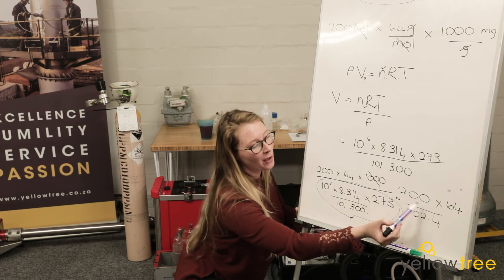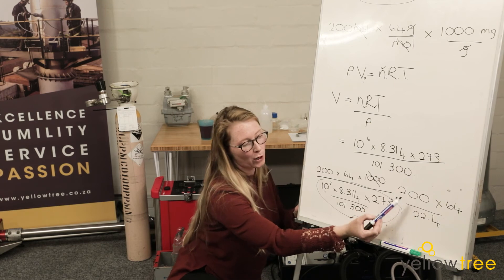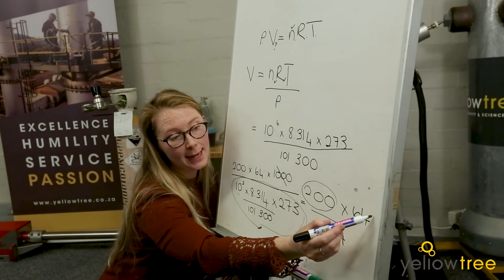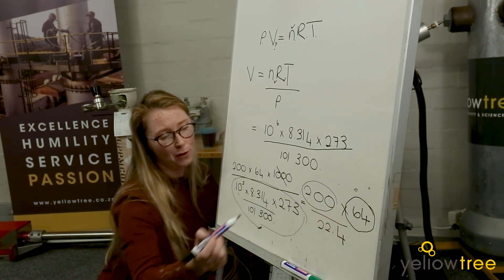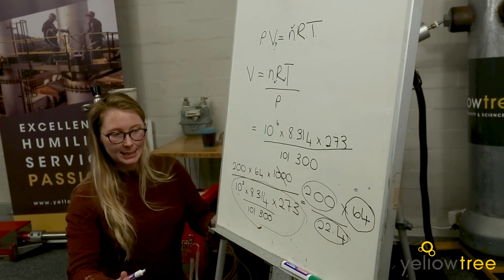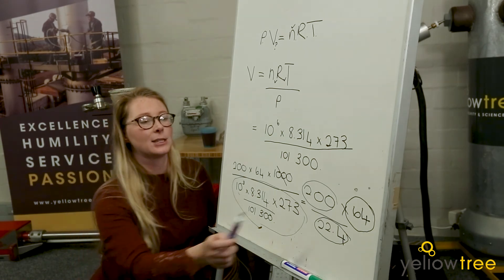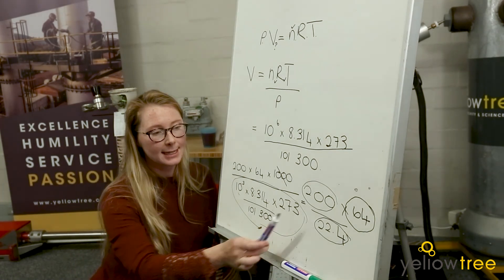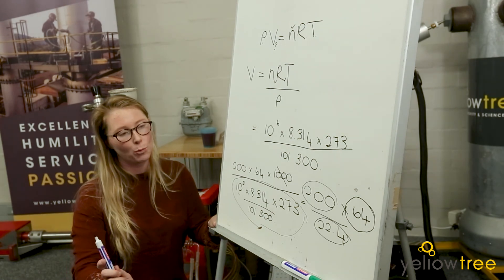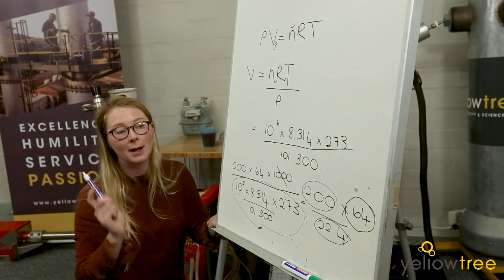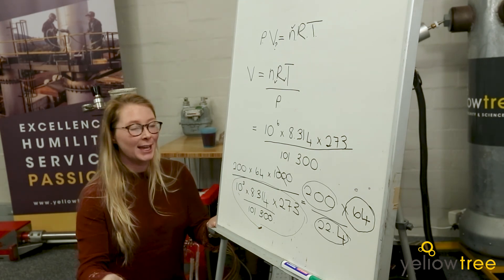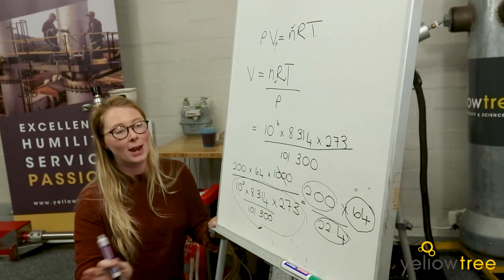So you can see we have the original ppm value we were working with — in this case 200. We have the molar mass of the gas — 64 for SO₂. And we have the number 22.4. Although there are all these calculations to get to this result, essentially all we need to remember when converting parts per million into milligrams per normal cubic meter is to multiply by the molar mass and divide by 22.4. That will work in every situation, no matter what gas you're using.